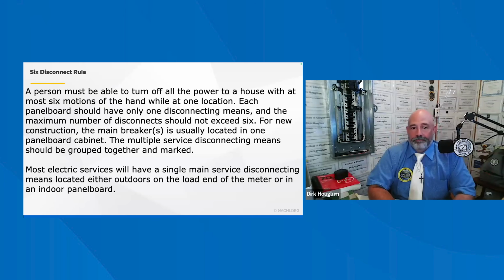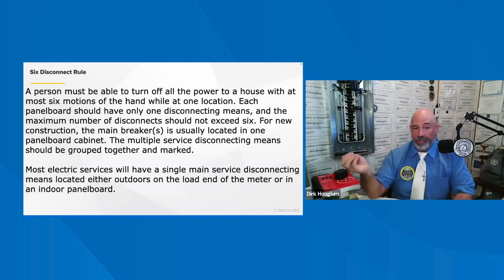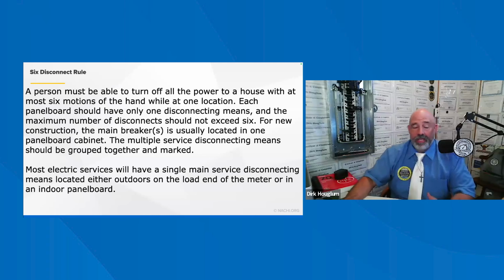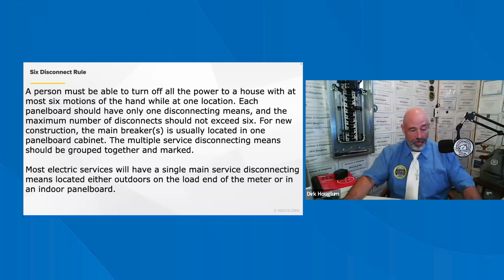For new construction, the main breaker is normally located outside. Multiple service disconnects should be grouped together and marked. Most electric services will have a single main disconnect outdoors, just in case something bad happens, so you can shut that off in a really quick hurry. And that's what we want to see.